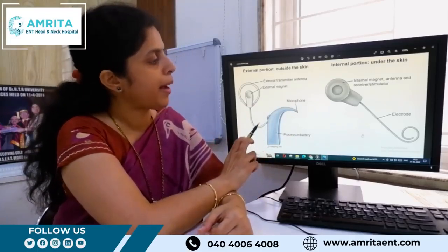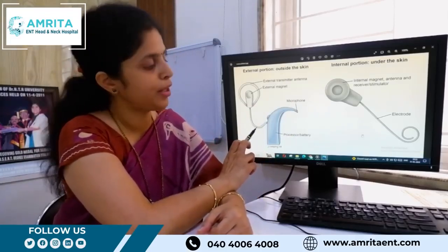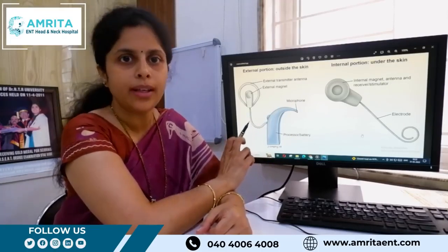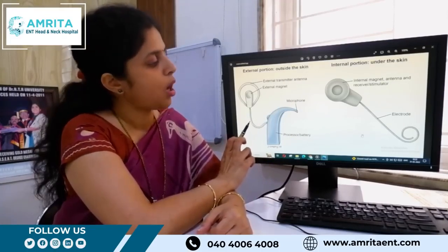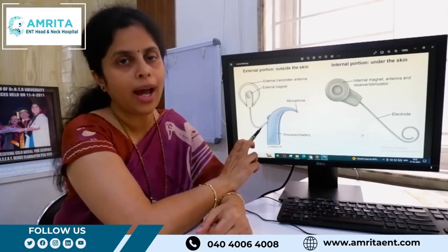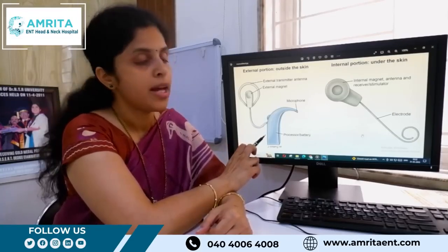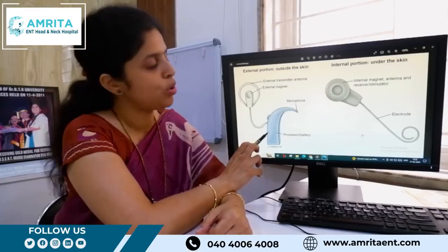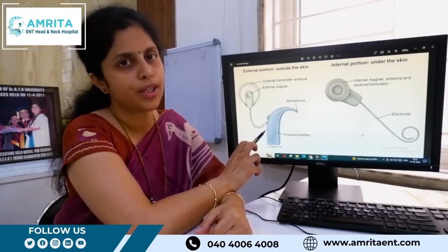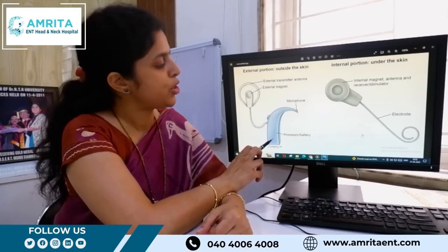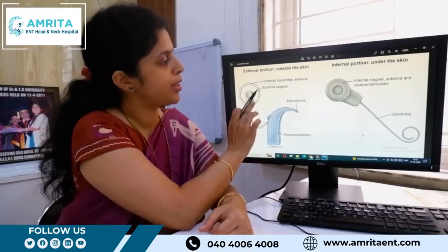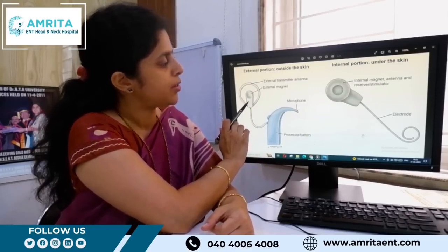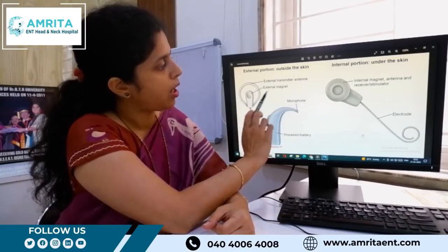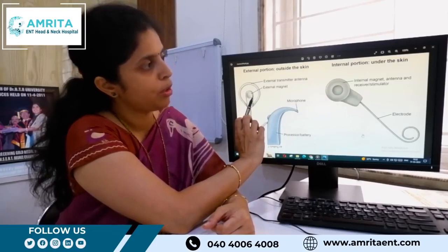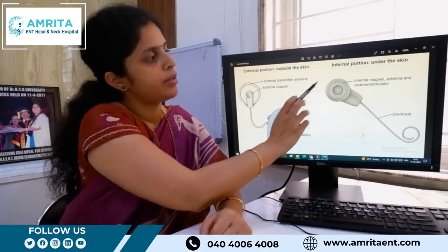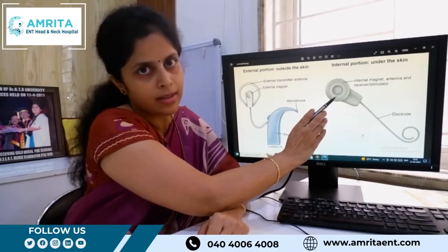The external part has a microphone, speech processor and a transmitting coil. So what happens when there is a sound in the environment? The sound waves are picked up by the microphone and are transmitted to the speech processor. The speech processor divides these sounds on the frequency basis and converts them into a digital signal. This digital signal is transmitted to the receiver through the transmitting coil. The transmitting coil and the receiver are held in position, attracted to each other by the magnet present in them.